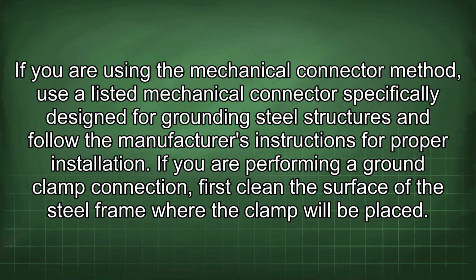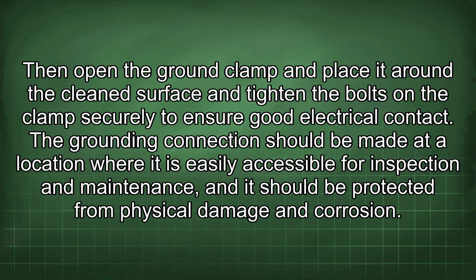If you are performing a ground clamp connection, first clean the surface of the steel frame where the clamp will be placed. Then open the ground clamp, place it around the cleaned surface, and tighten the bolts on the clamp securely to ensure good electrical contact. The grounding connection should be made at a location where it is easily accessible for inspection and maintenance, and it should be protected from physical damage and corrosion.